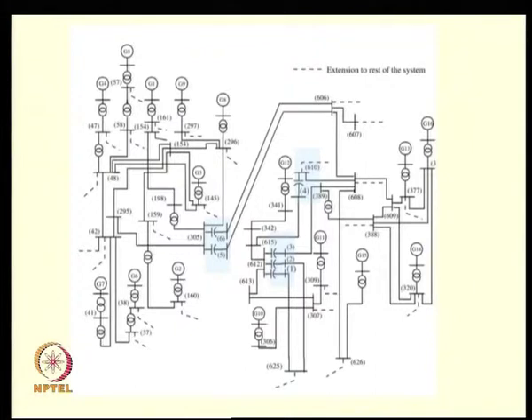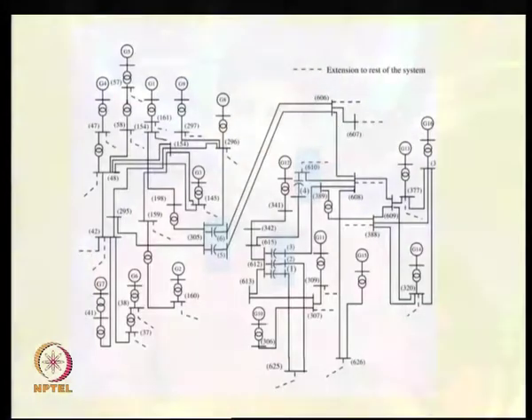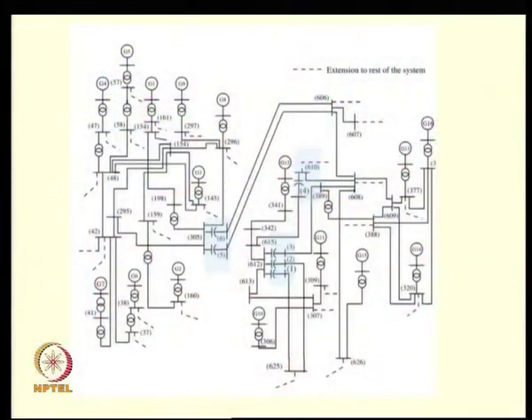Hydro turbines have a relatively large generator mass compared to the turbine mass, which is not true for steam turbine generators. In such situations, the electrical torque does not have as much controllability over the torsional modes. These statements are made without detailed proof here as it is beyond the scope of this course. For more detail, I request you to go through the literature, especially Padiyar's book and Kundur's book.